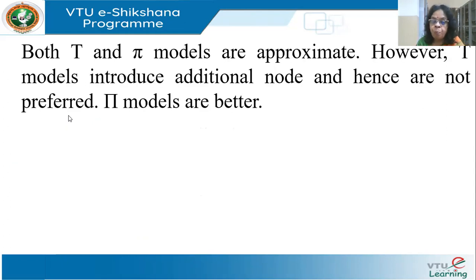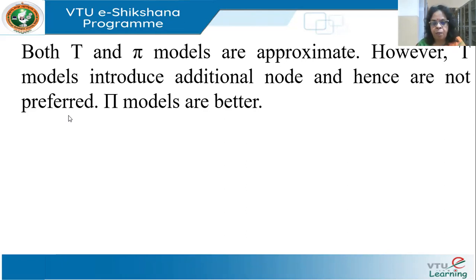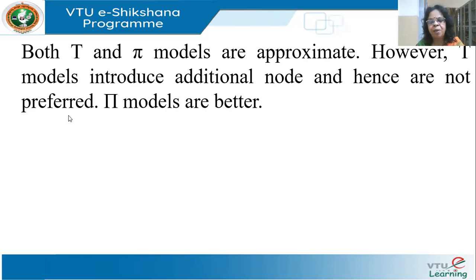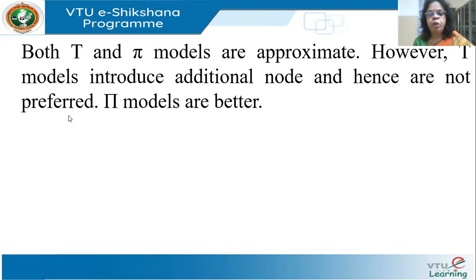Please remember both T and pi models are approximate models because we represent distributed parameters with lumped parameters. However, in the T model you get an additional node at the center which doesn't exist in the physical system. Hence, pi models are very popularly used for load flows, transient stability analysis, short circuit analysis, and building the bus admittance matrix, which you will deal with in later power systems courses.